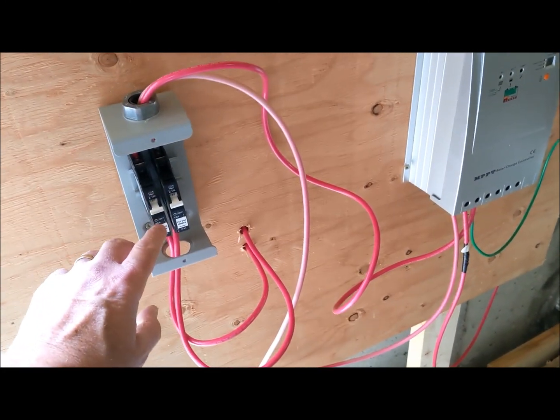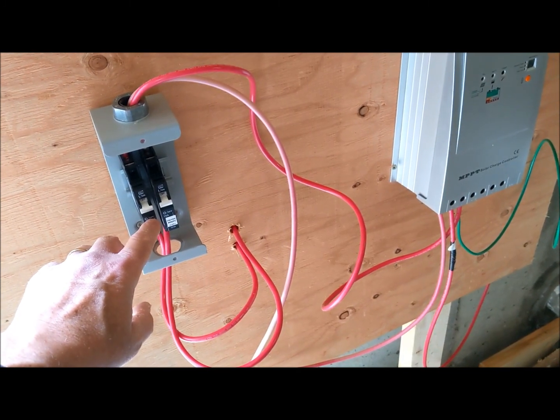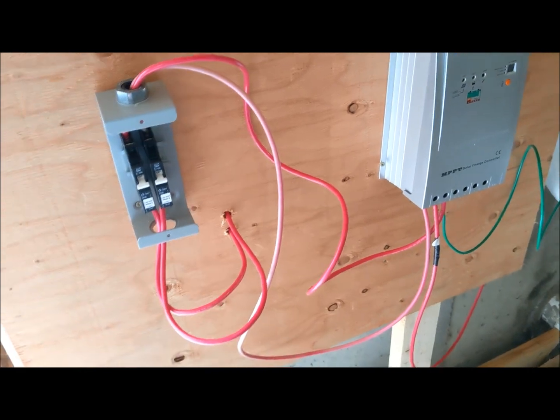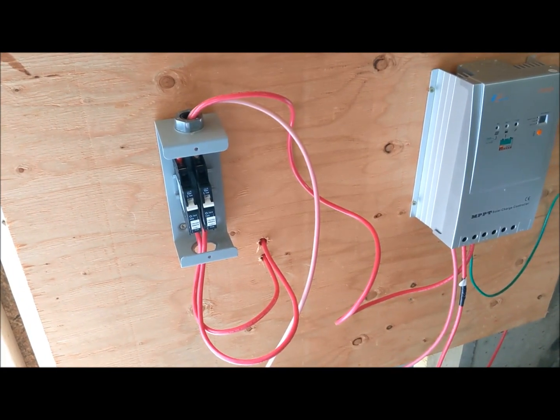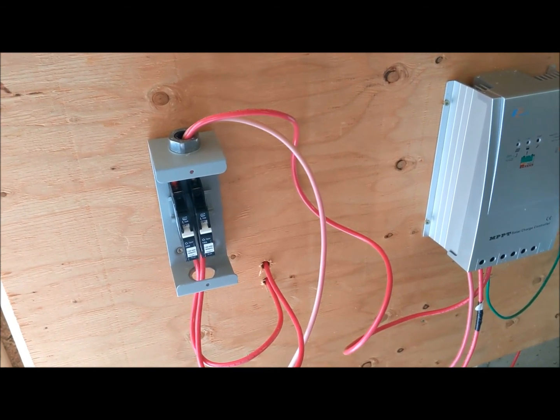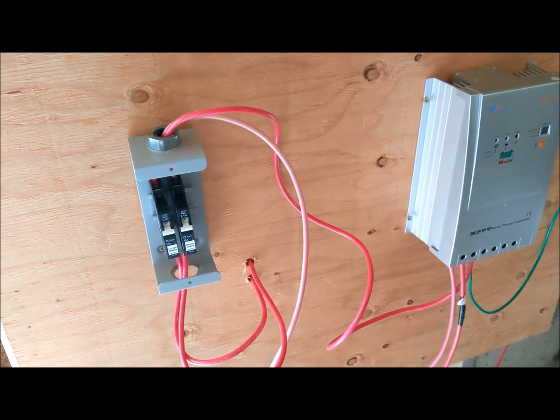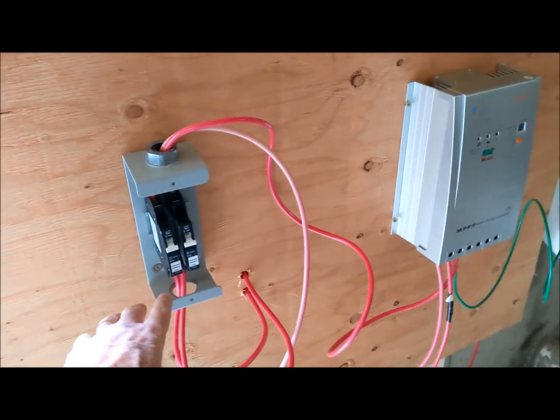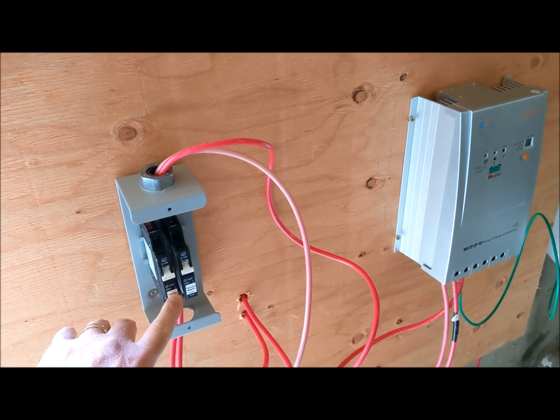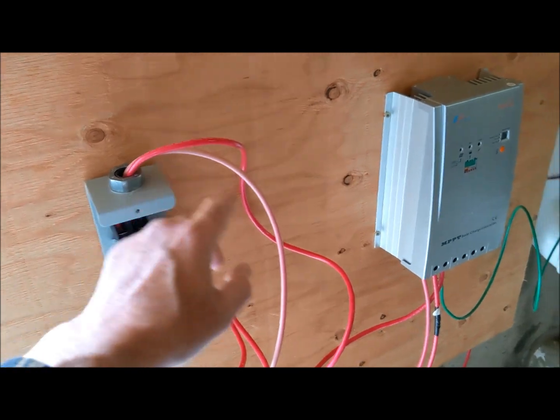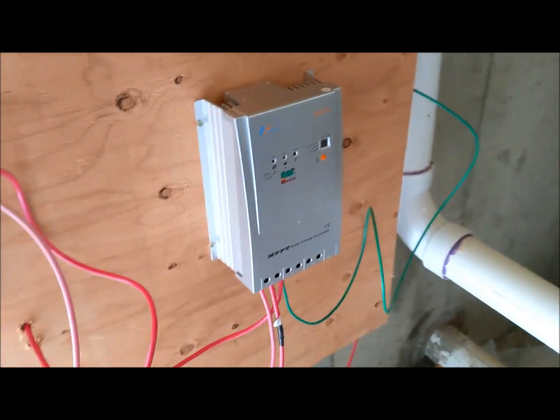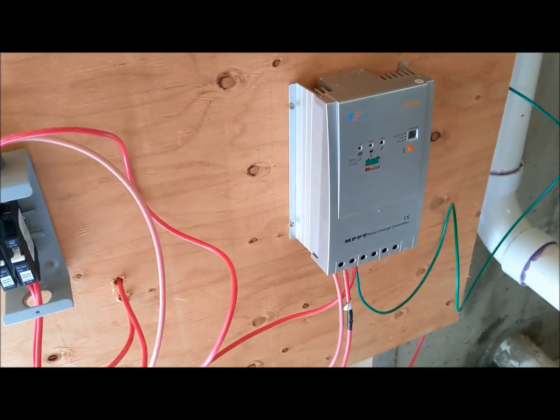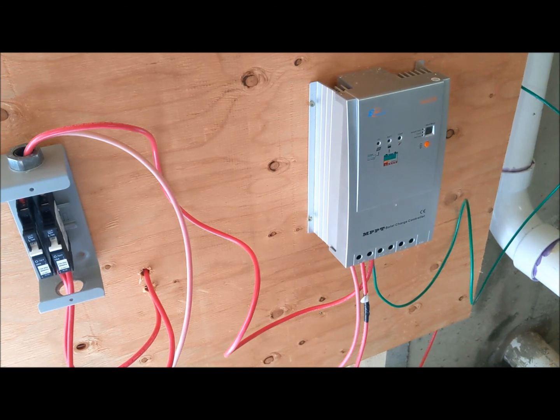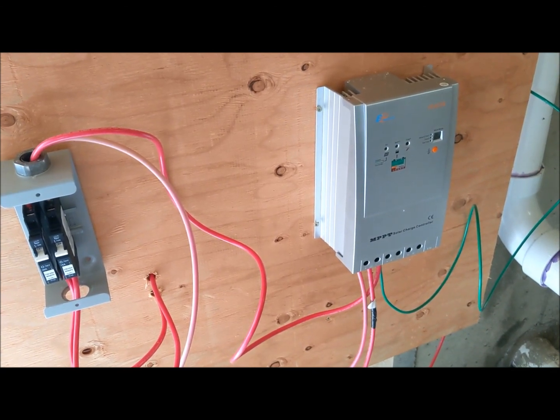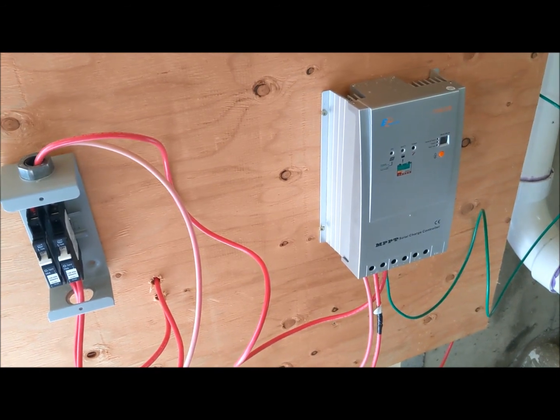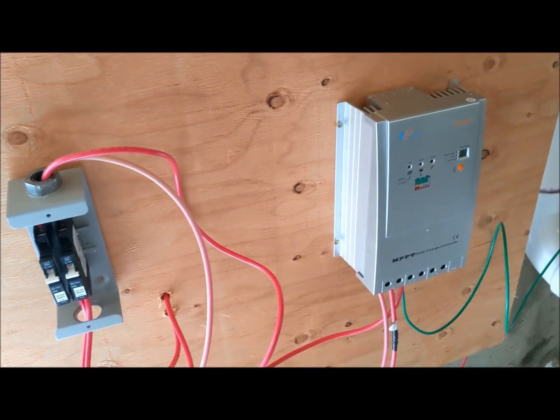This other breaker goes to the battery, and on the battery, even though it's set up for right now 12 volt battery, eventually I'm going to change the configuration to 24 volts. You want the positive side of the battery to come into the positive side of this DC breaker, and then from there it feeds over to the charge controller. The reason they do that is if something goes wrong and the charge controller shorts out, the massive amount of current is coming from the battery. So that's essentially at a higher potential than the charge controller.